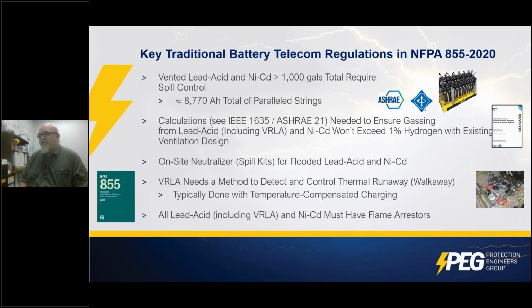Back in the old days, we called it thermal runaway, and then we learned what thermal runaway really was when lithium-ion came along. So we've been renaming thermal runaway in lead acid batteries, mostly VRLA, thermal walkaway, because it's very, very slow. The way that's typically handled is with temperature compensated charging. And then all lead acid and NiCad have to have flame arresters. Next slide.